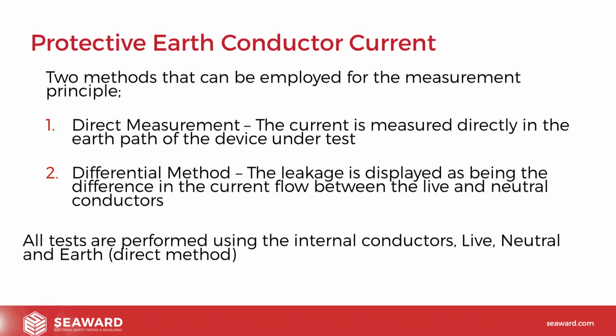The advantage of the differential method is that the current, or any kind of external paths to earth, do not have to be eradicated in this case. So if there was a path on a product that led to a pipe, and that pipe flowed to earth, we wouldn't need to disconnect that, because now we're just seeing exactly what the difference is between the two conductors. So any leakage, wherever it's flowing away from the instrument, will be picked up via the differential method. As I say, it's not really something to worry about.